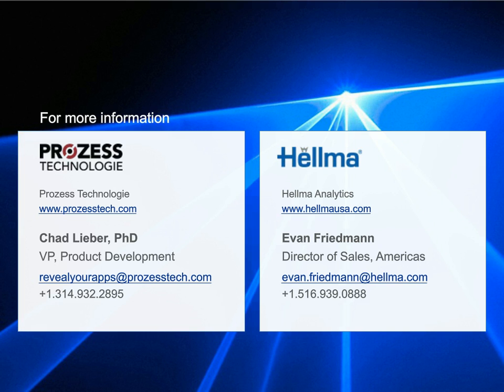And what is the spectral range of the Prozess system, and what is the resolution and spectrometer used? Sure, I had mentioned that briefly. We have a number of UV spectrometers that we'll use depending on what the other purposes of the device will be. But all of them start at 190 nanometers and extend longer from there. So we have a 190 to 400 option that provides fractional nanometer resolution. We have a 190 to 600 nanometer option, as well as a 190 up to around 1 micron solution, where certainly the range and resolution trade off.